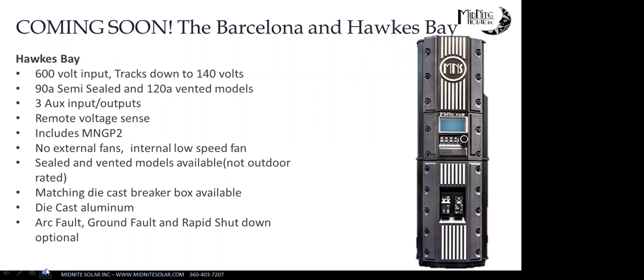And they will be arc fault, ground fault, and rapid shutdown modules that you will plug in as option boards. The ground fault meets all the new standards where you can actually solidly ground the negative and it will still work because it's measuring the differential current. So this one's really cool. It's really close. It's working really well.